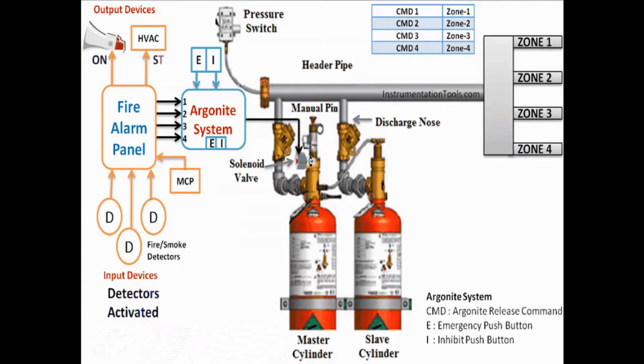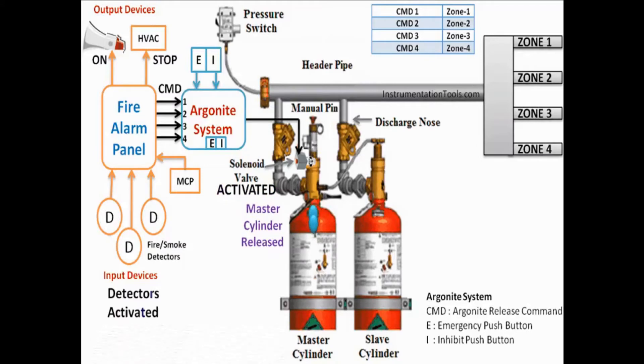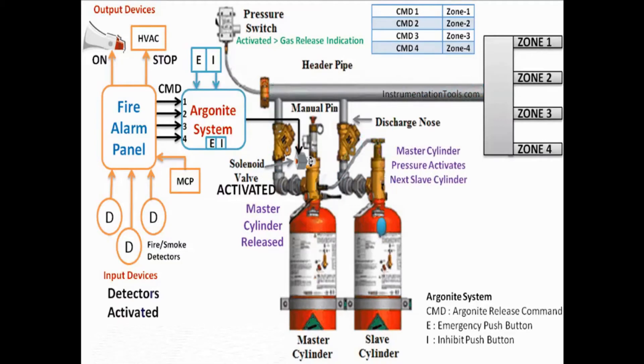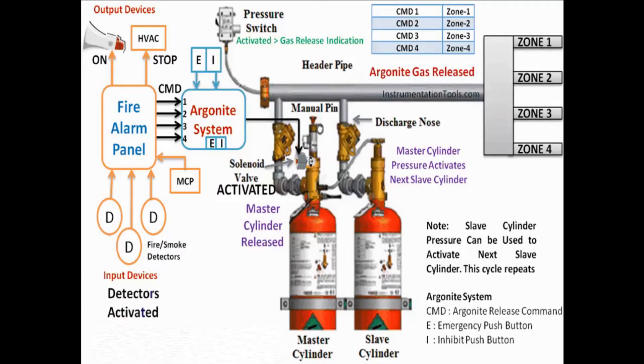The argonite system receives the release command from the fire alarm panel and waits for some time before releasing the argonite cylinders — typically from 30 to 60 seconds. Sometimes we receive false fire and smoke detector alarms; in that case we have to inhibit the argonite release command. Inhibit means stop the action. Inhibit push buttons are generally installed near the argonite system or respective zones, and are also provided on the argonite panel.